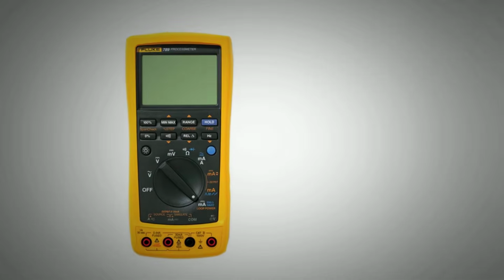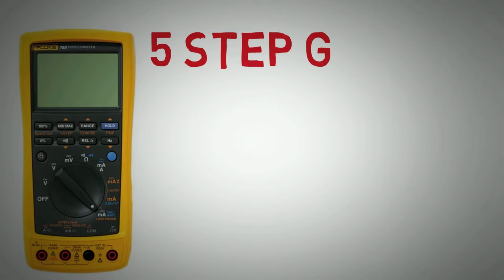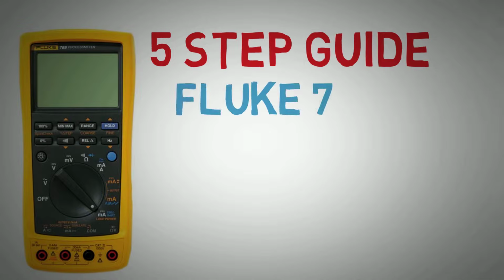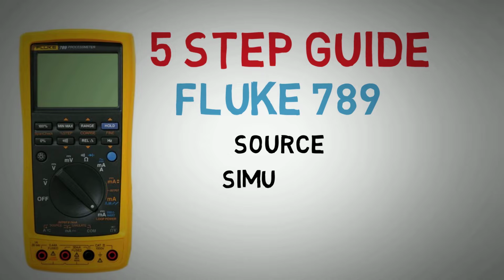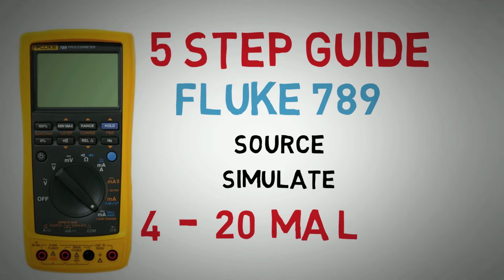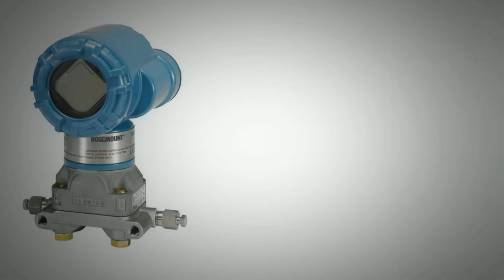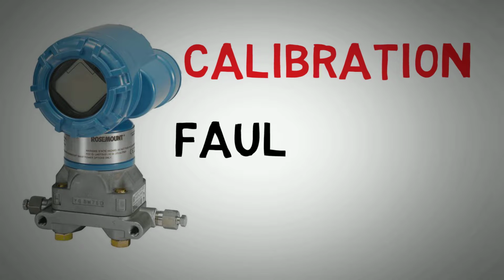I'm going to show you an easy to follow 5-step guide to using a Fluke 789 process meter for sourcing or simulating 4 to 20 milliamp loops. Perfect for a whole host of instrumentation, calibration and fault finding needs.